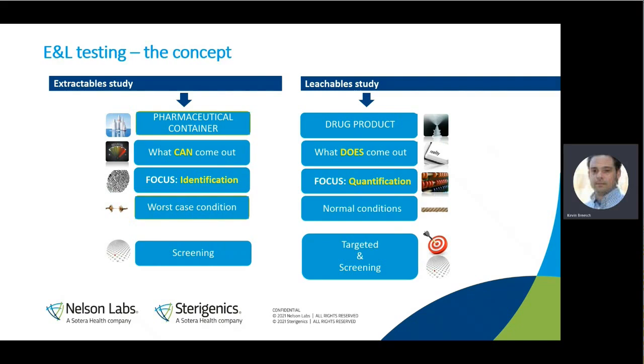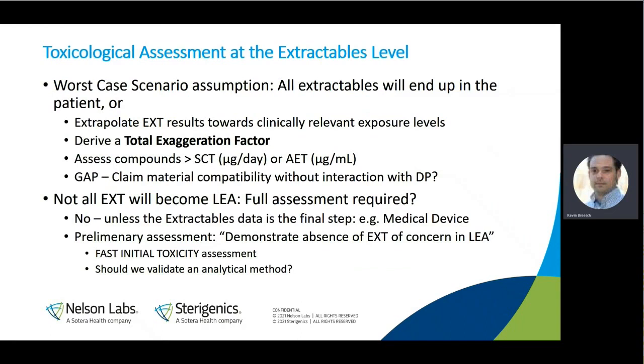So let's start with assessing the extractables data. From a worst case scenario, we can assume that all extractables will end up in the patient. This is obviously not the case, but one could assume this. Or we can try to extrapolate the extractables data towards a more clinically relevant exposure level.